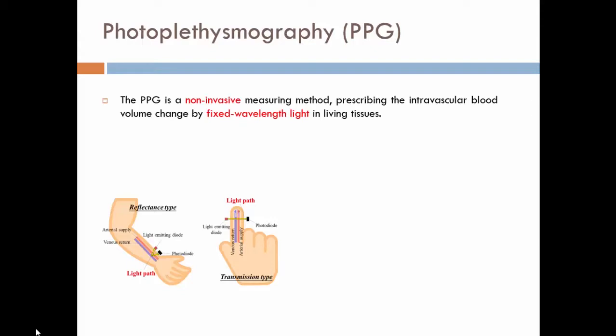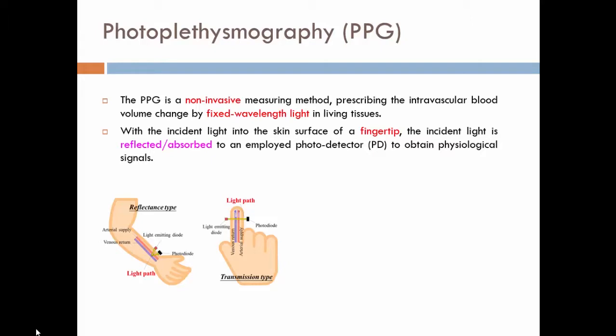The PPG sensor essentially consists of two different components: LED and PD. So LED will emit the light going under the skin. Hopefully you will reach the blood vessel, which you would like to detect, like radial artery. Then the lighting power reaching the blood vessel is going to be reflected back to the skin surface and reaching another component of a PPG module, which is PD.